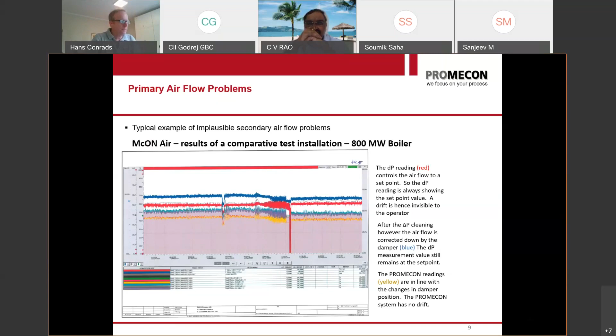Everyone can see that at the middle, the red line starts to swing and get very noisy. In this case, the user has cleaned the impulse lines to get a nice signal again. However, if you look at the blue line, which is the damper controlling the air, you can see the damper before cleaning was higher than after cleaning. Every delta P measurement drifts, and in your power stations, all your delta P measurements are drifting. There is not a single delta P measurement that is not drifting. And that's the second big finding. So your feeders are wrong and your airflows are wrong. And that's the reason why you have high NOx, low efficiency.